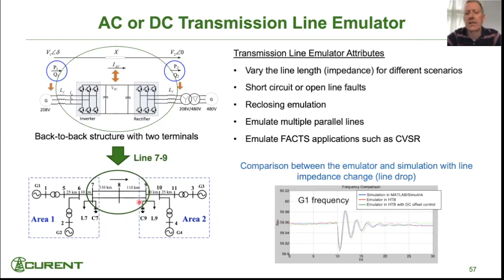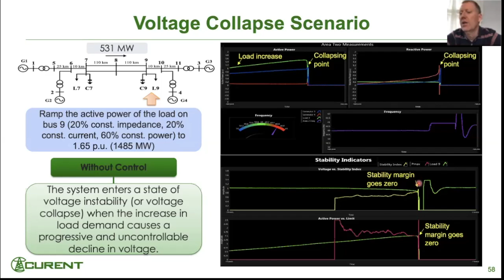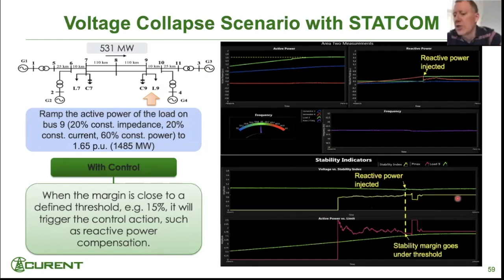This is showing a scenario where we're transferring power over a long distance. As we increase the load, eventually we're not able to do that because we're not able to regulate the voltage well, and you hit what's called a collapse point. In CURENT, we developed a tool to predict where that occurs, meaning where our stability margin goes to zero. The reason we did that is, of course, you want to avoid it. You can avoid it by, when you get close, injecting some reactive power to help regulate the voltage, so you can continue to increase the power you're sending from one end to the other and maintain a safe margin to keep a stable grid.